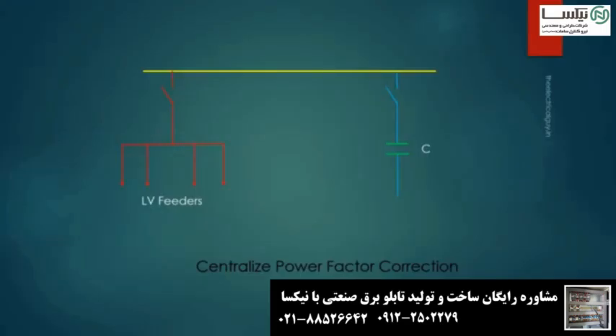Centralized power factor correction. In a system, not all loads are connected for all day. There are some loads which are connected for a very short time. In such cases, the use of distributed power factor correction is not a good choice. In such cases, centralized power factor correction is preferred, in which capacitor banks are located at the origin or at the center of the system. This allows a remarkable reduction in the total power of the installed capacitors. The capacitor banks must be installed with a switching device, as keeping the capacitor bank connected permanently to the system is not a good choice.